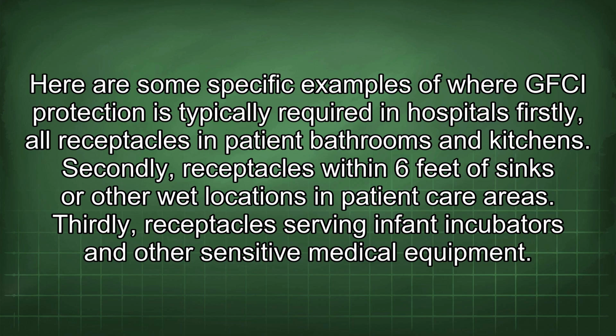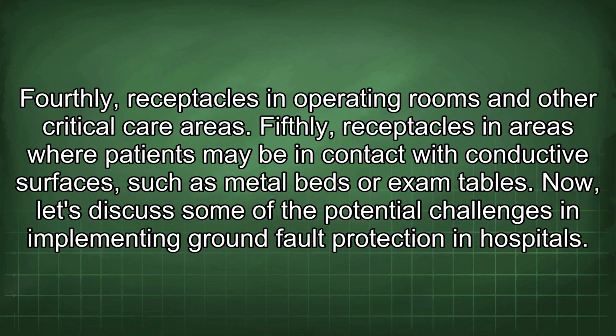Here are some specific examples of where GFCI protection is typically required in hospitals. Firstly, all receptacles in patient bathrooms and kitchens. Secondly, receptacles within 6 feet of sinks or other wet locations in patient care areas. Thirdly, receptacles serving infant incubators and other sensitive medical equipment. Fourthly, receptacles in operating rooms and other critical care areas. Fifthly, receptacles in areas where patients may be in contact with conductive surfaces, such as metal beds or exam tables.